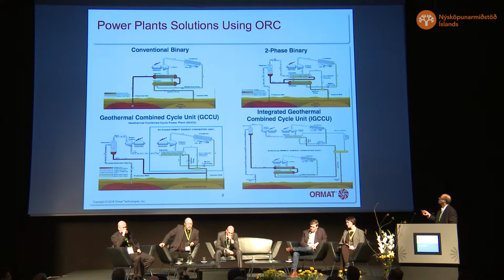The binary can also use two-phase steam and brine. Steam generally feeds the vaporizer, and brine goes to the preheater, and then a combination of a steam turbine and a bottoming ORC. The steam first enters the steam turbine, and the exhaust at above atmospheric pressure goes into the bottoming cycle. With the integrated geothermal combined cycle unit, we also use the brine for a brine ORC.